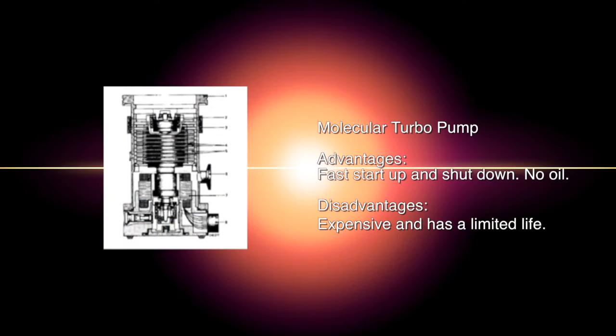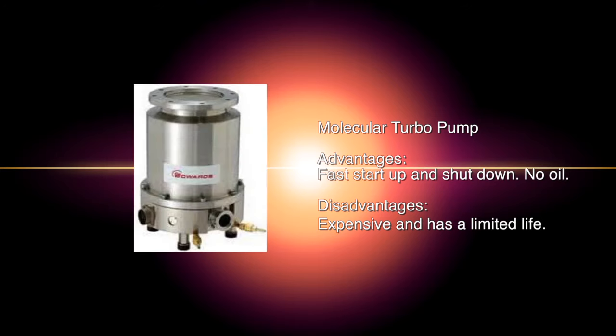Molecular turbo pumps have largely replaced diffusion pumps in the vacuum technology industry. Their main advantage being that they have fast start-up and shut-down speeds. There's no hot oil to heat up or cool down or contaminate the vacuum system. They are, however, a lot more expensive and have a limited life expectancy compared to that of the diffusion pump.